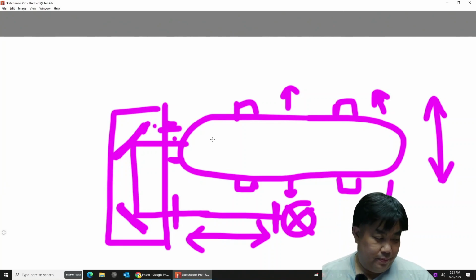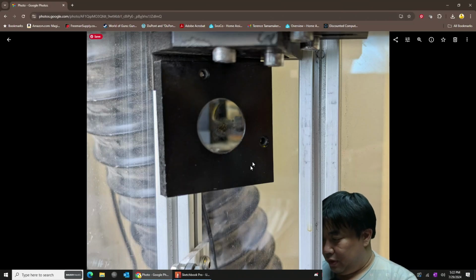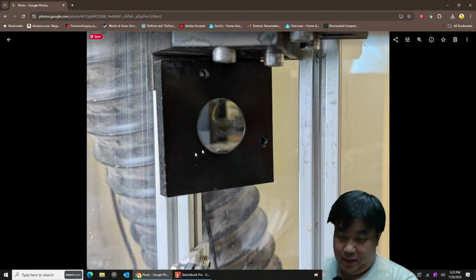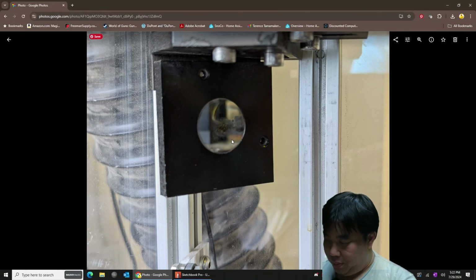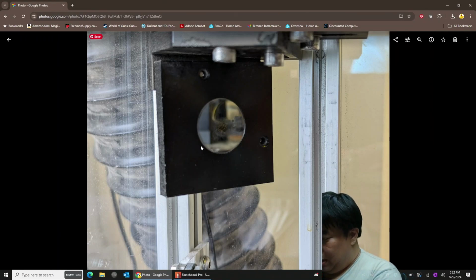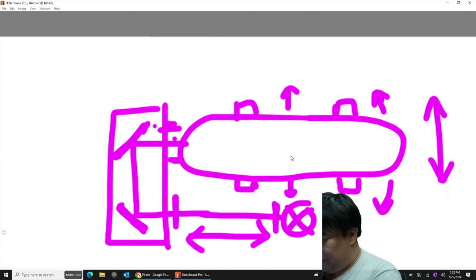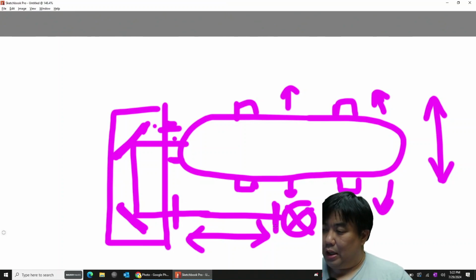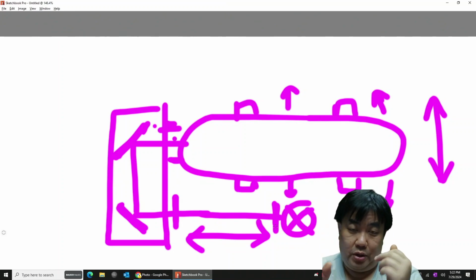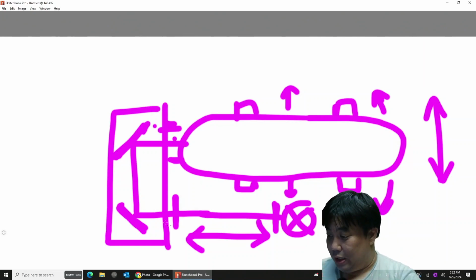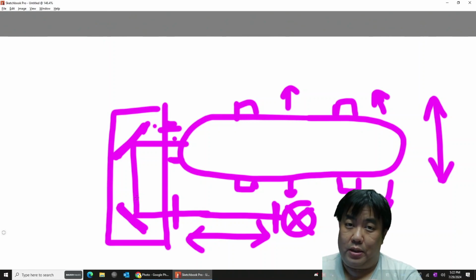So the advantage of doing it this way is you're not going to have any sort of mirror fouling issue. So this is an example of the fouled first mirror that you see on our laser. Because the optical path is sealed, dust won't be able to get in, so this wouldn't be a problem. The other advantage is that if you do need to replace parts, these two optical windows don't carry any sort of special alignment requirements. So we should be able to just unscrew the optical window. If these do get fouled, we can unscrew it and screw a new part in without having to go through the recalibration process.